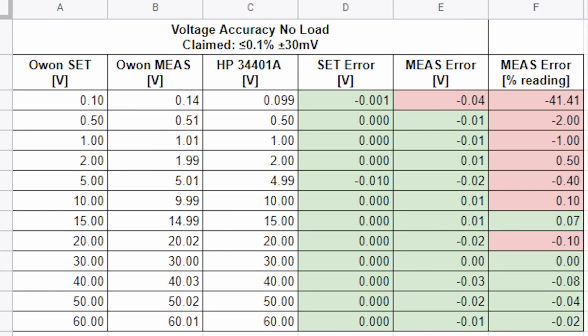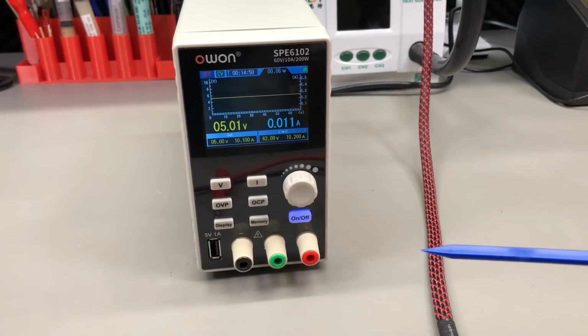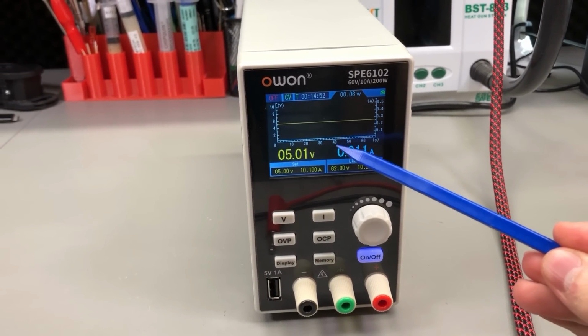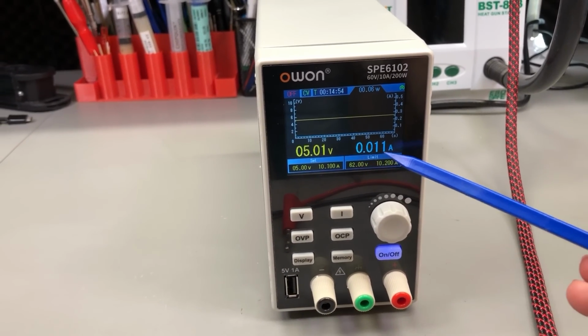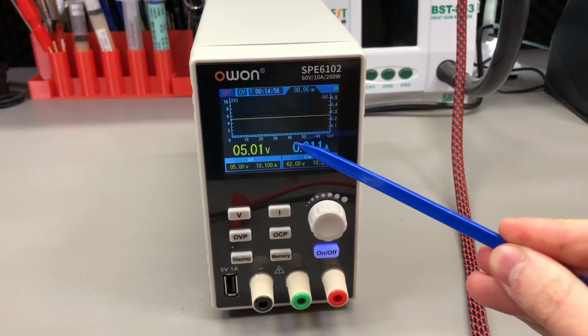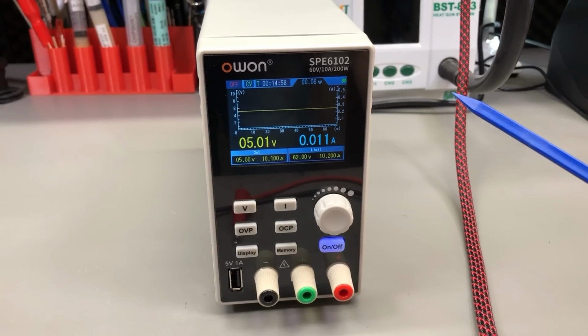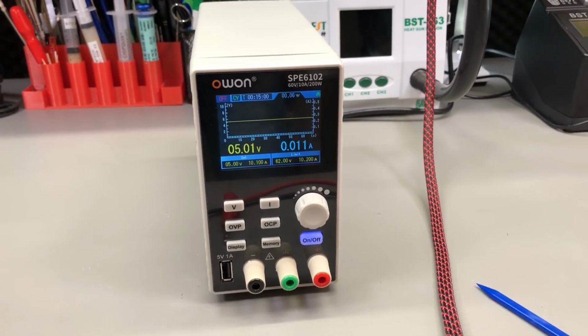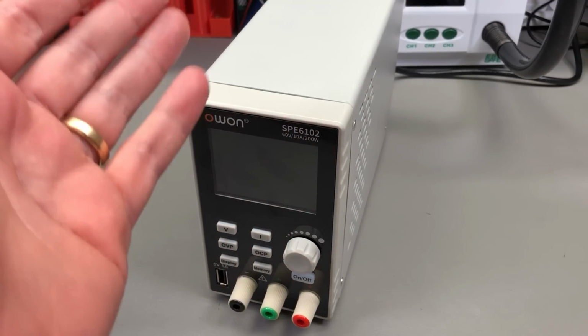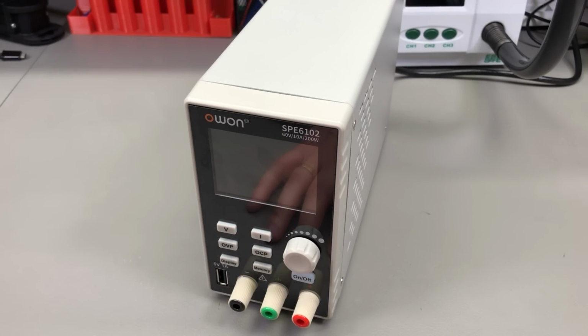That is even more visible if we calculate error as a percentage of reading. Now, a good chunk of this error correlates to that constant current offset shown on the Owon screen. It may be that it just needs calibration, and it once again might support the theory that they're using two separate measurement points, one for the set and control loop and another one for the display. But I can't find any good reason why they would do that. And if you wanted to somehow correct for this, there doesn't seem to be any user accessible calibration function, at least not mentioned in the user manual.